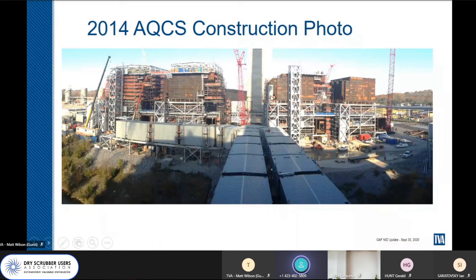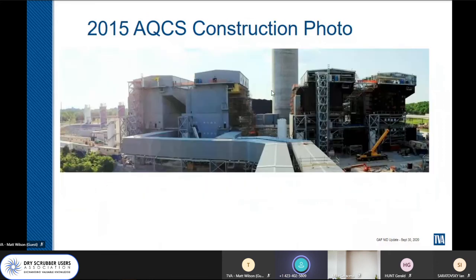So this is the inlet NID J-duct reactor, and this whole reactor, this is where the dry scrubbing takes place predominantly. This is lined on the interior with AR350 plate. That's abrasion resistant plate. It's not an ASTM standard, but that seems to have held up well during the operation to prevent erosion of this really particulate loaded area, high velocities and a lot of particulate going on right here in this reactor duct.